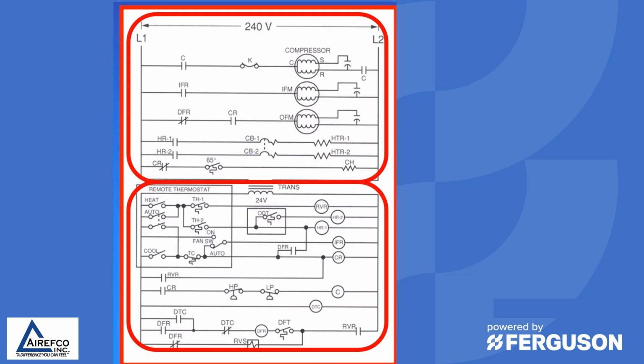On some diagrams, you may have multiple control voltages, where you may have 240 volts for the line voltage. You could have a 115 volt control circuit with a 24 volt control circuit. So make sure you understand what kind of circuit you're working with before you start working on it or trying to troubleshoot.